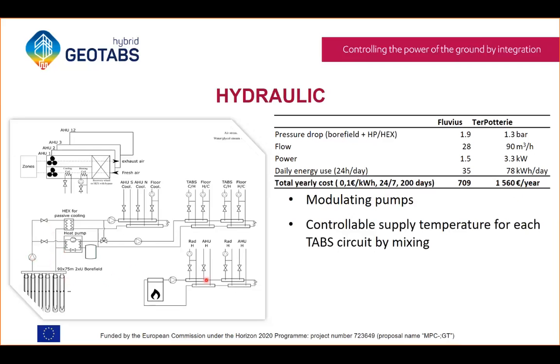A second important aspect, which is also a general guideline for MPC, is that we need a higher degree of freedom. The more freedom MPC has, the more optimally it will be able to behave. So when we have TABS with north zones and south zones with different heating and cooling needs, it's interesting to separate them into two different circuits and enable recirculation of the return water, so that we can have different supply temperatures for each circuit and provide different amounts of heat or cold for different zones.